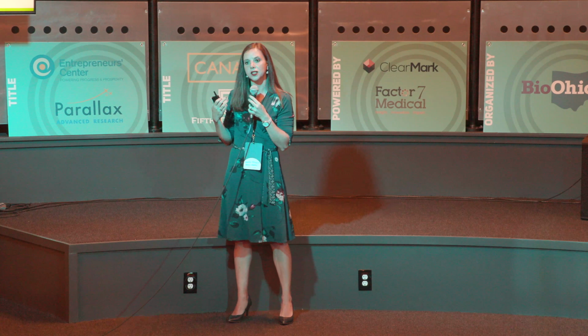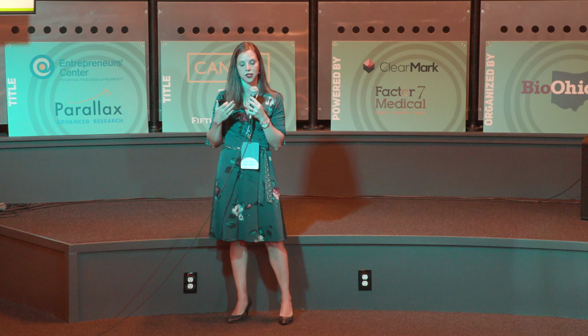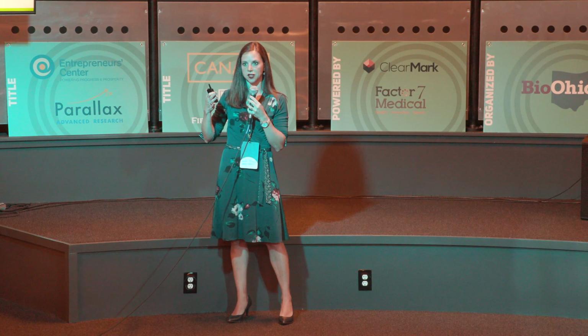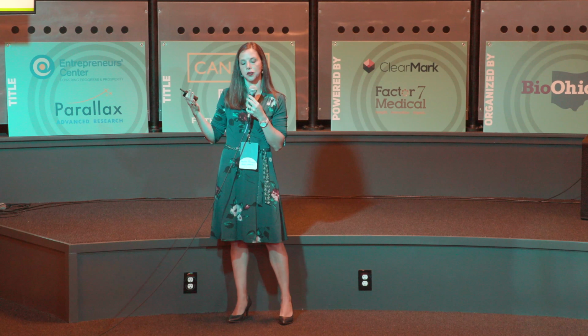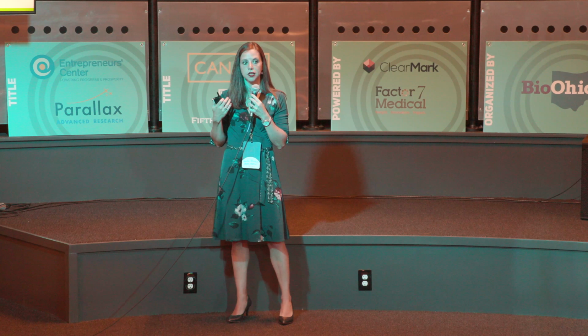There's bench and mechanical testing. There's either ASTM standards, these protocols are well thought out and FDA is very familiar with, or you need to evaluate your device. What are the different steps that your device is going to see once it's being used with a patient, and you have to identify what appropriate protocols and testing needs to go into the device so that you can present that information to FDA.